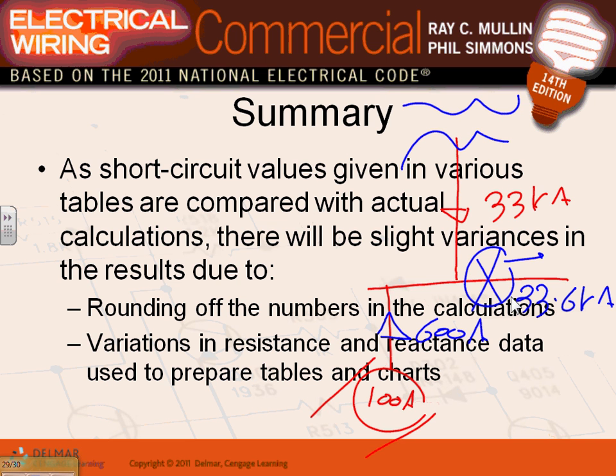So yes, your highest is 33 kiloamp, but if you have more motors, this contradicts what I told you before. I said the one closer to the transformer is always higher, right? Unless you have a lot of motors. If you have a lot of motors, you could end up here with higher than here, like we did, 33 coming from the transformer, but inside the switchgear is 33.6. Have a generator, even worse. Your equipment motors will act as generators upon the existence of a short circuit condition and pump more current into the system. Just remember this as we move on.